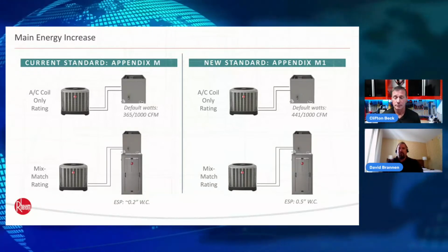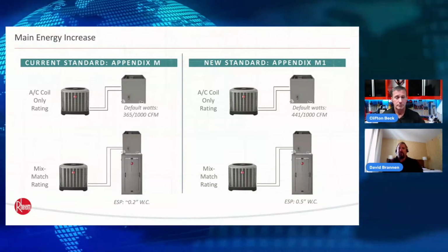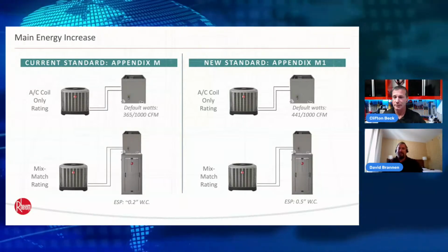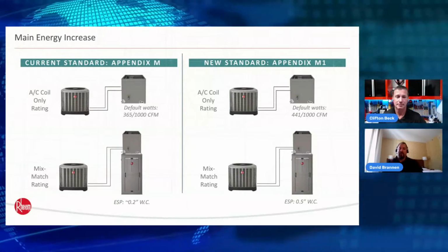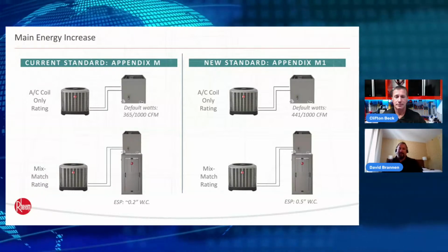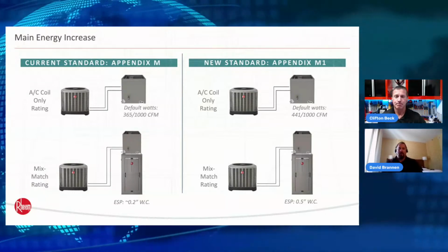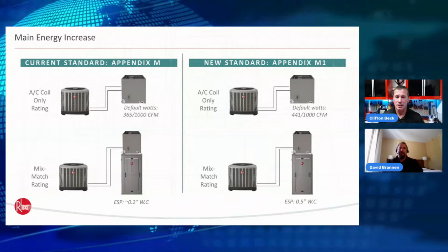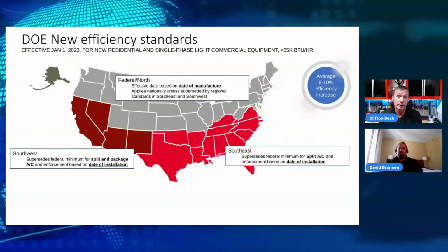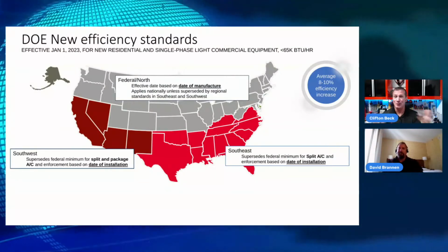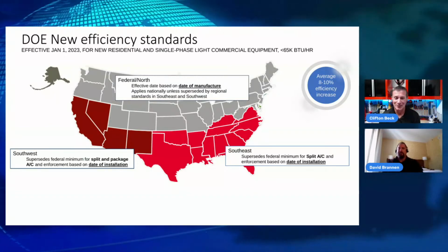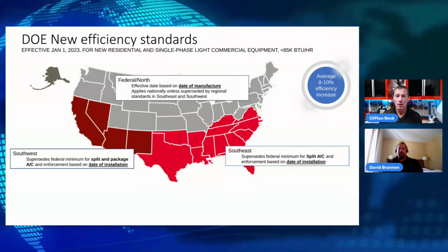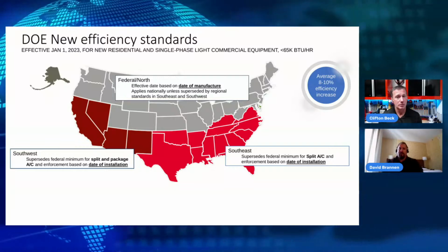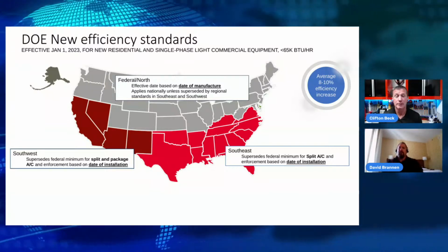The industry here has been flex duct and ductboard for forever, a good 10 to 15 years, and you just don't see them installed at 0.5. Very, very rarely. I've seen many well above 1.0 on new installations, done site visits exactly like you've been doing today, going out to look at a piece of equipment and go, well, it can't perform when it's outside of these parameters. So a much different parameter set to work with.